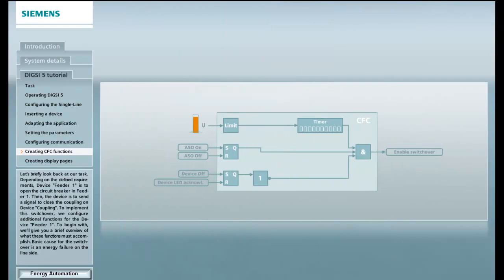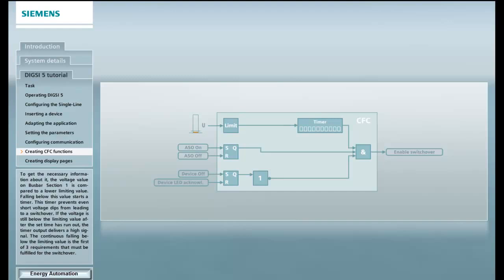To begin with, we'll give you a brief overview of what these functions must accomplish. Basic cause for the switchover is an energy failure on the line side. To get the necessary information about it, the voltage value on bus bar section 1 is compared to a lower limiting value. Falling below this value starts a timer.